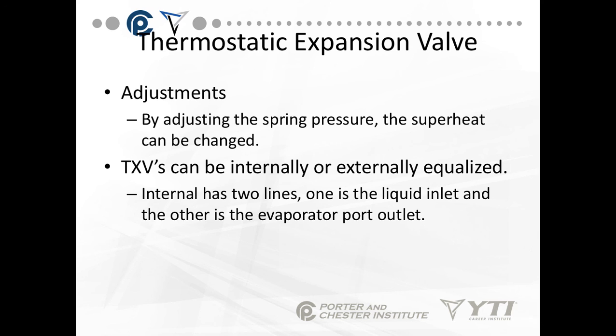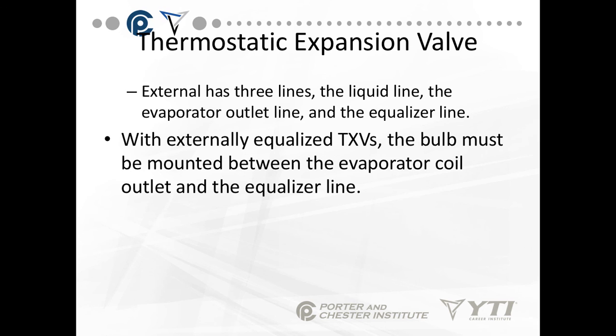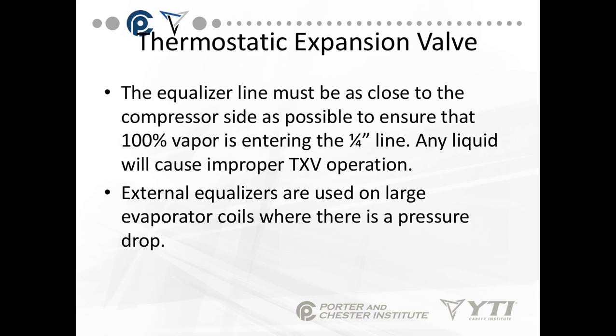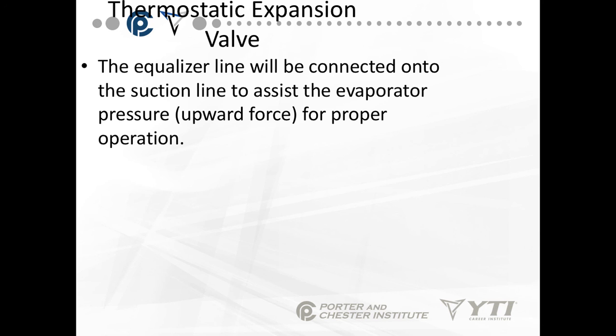Internal equalization has two lines: the liquid inlet and the evaporator port outlet. External equalization has three lines: the liquid line, the evaporator outlet, and the equalizer line. With externally equalized TXVs, the bulb must be mounted between the evaporator coil and the equalizer line — not on the compressor side. If you put it after the equalizer line, you will not get correct temperatures. The equalizer line must be as close as possible to the compressor side to ensure 100% vapor is entering the quarter-inch line. Any liquid coming back through the external equalizer will cause improper TXV operation. External equalizers are used on large evaporator coils where there is a pressure drop, and the equalizer line is connected to the suction line to assist the evaporator pressure for proper operation.